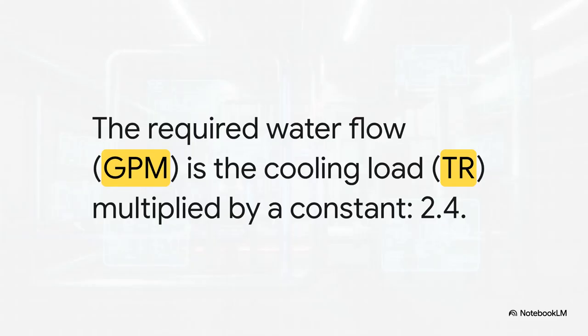Now, what's so cool here is how simple the main formula is. The water flow you need in gallons per minute, or GPM, is just the cooling load in TR times 2.4. And that 2.4 isn't some random number. It's a constant that comes directly from the physics of water, its specific heat, and a standard temperature difference used in these systems. This little formula is the absolute starting point for every single design.